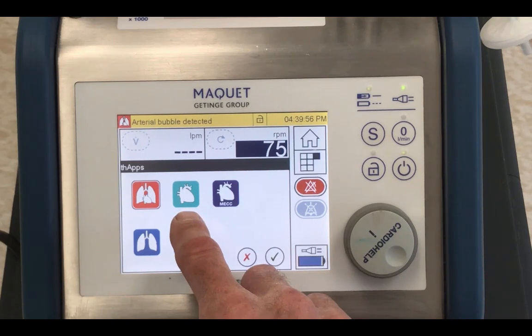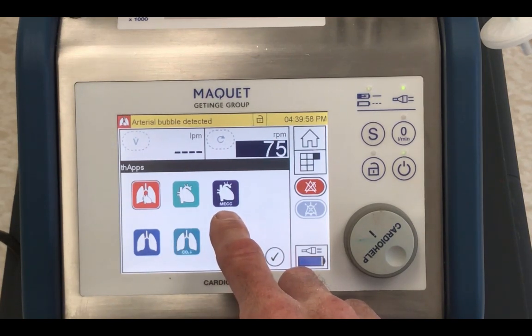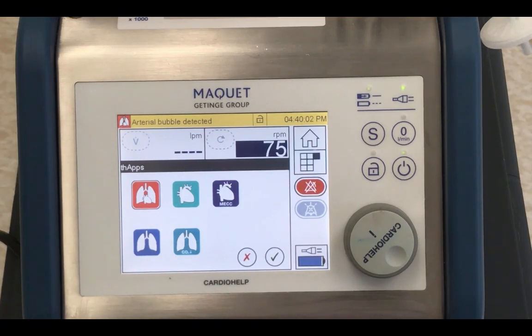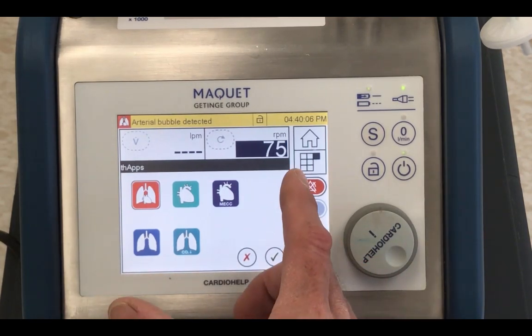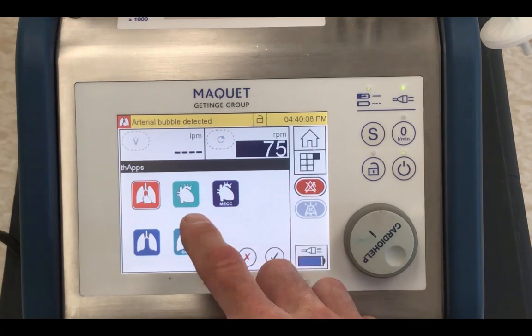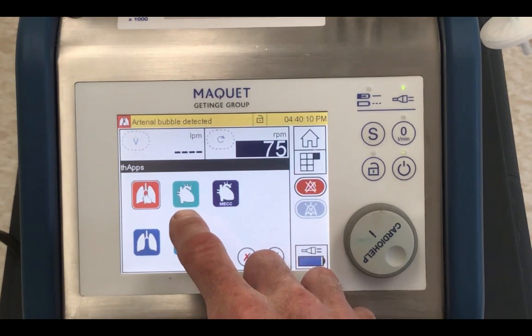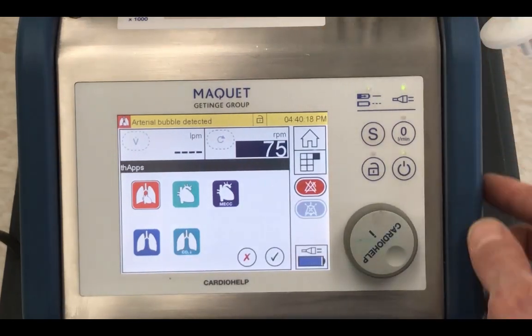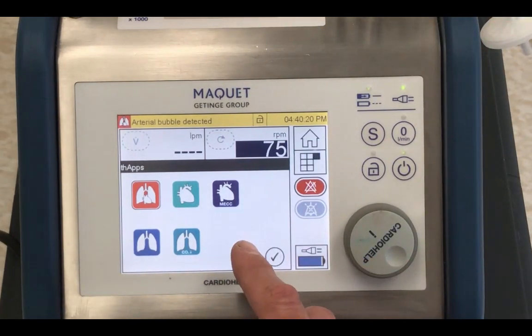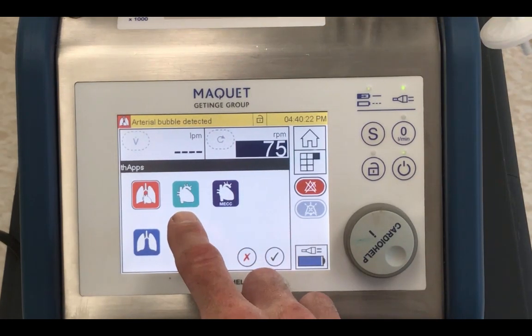It has a picture of a heart with a teal background, and it's got a picture of a heart with a purple background, and it says MECC. And if you were to put these into applications based on where you're going to use this device, this is designed as a ventricular assist device. This is not available in the USA, but in the UK, they have disposable sets for this pump. They have only a pump and they have no oxygenator, and that would be your VAD mode.